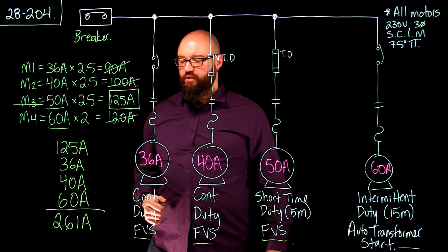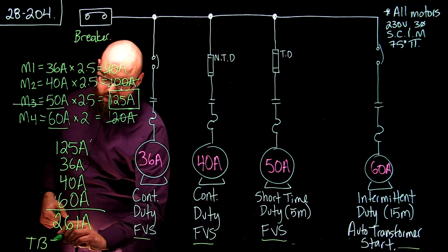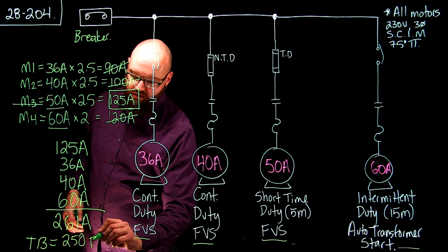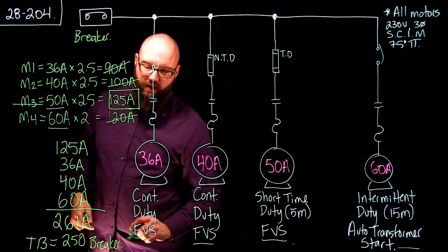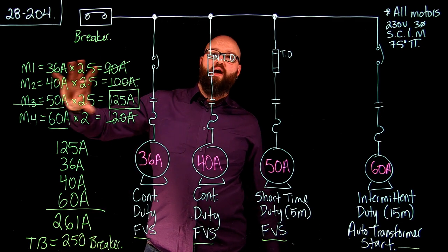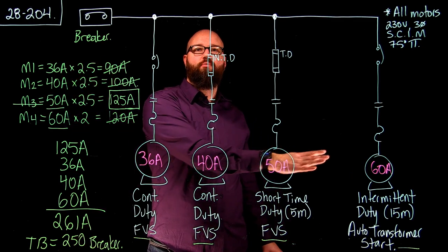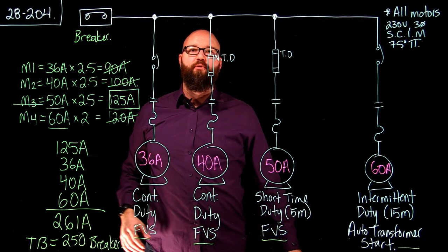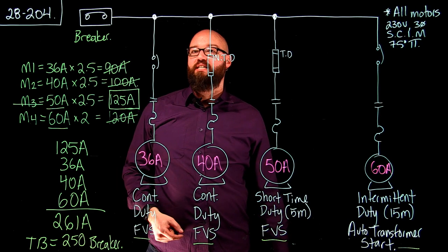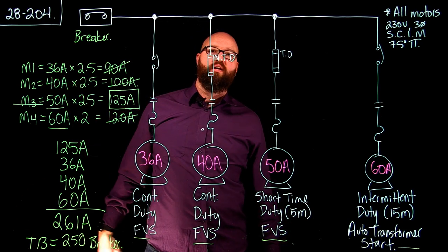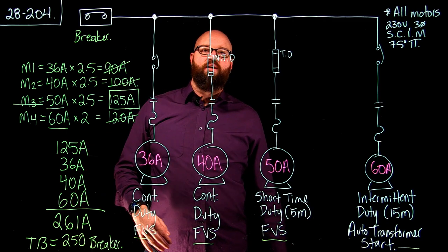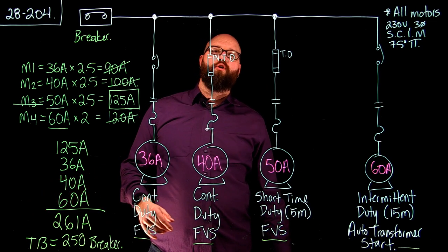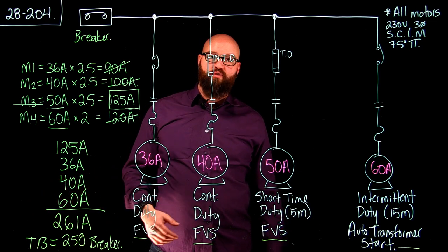Rule 28.204 tells me I cannot exceed this value, so we're going to go to Table 13. To protect this entire bank of motors, we're going to select a 250-amp breaker. To recap: calculate the value for each individual motor based on the main overcurrent protection type using Table 29. Take the highest calculated value, disregard the rest, add the remaining FLAs, and that gives the maximum setting. Then pick the overcurrent device going down to the next available size.